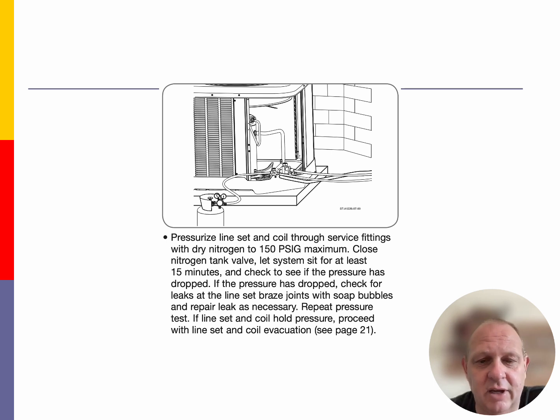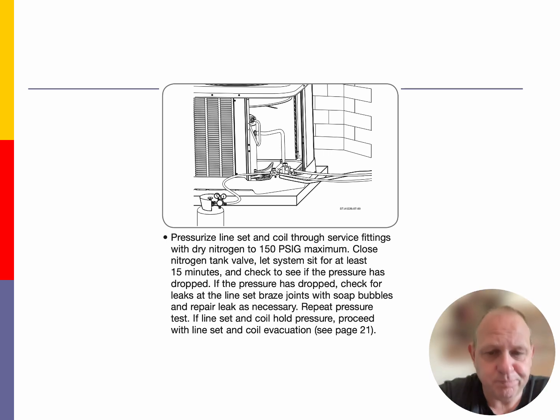Mini splits are a different monster. If you're pressure testing those, you might have to open up the LEVs on those, because there's no port on a Mitsubishi unit when it comes to that. So you have to look at specific items such as that. And I just encourage you, as you are installing units out there, to read the manuals on them.